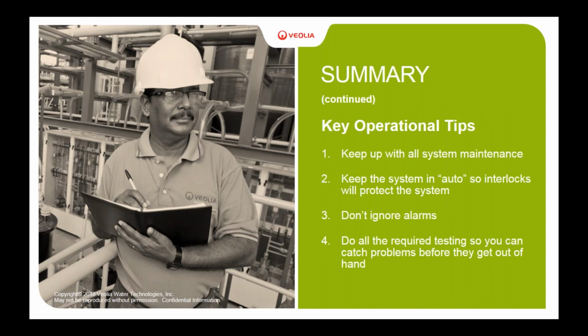Some operational tips that we went over. A lot of this has to do with keeping your system maintained properly. If that's the operator himself or the maintenance department: keeping pH probes calibrated on a daily basis, keeping heat exchangers cleaned, making sure boilers' preventative maintenance work is done, etc. If the system is maintained well and everything is functioning properly, your reactor should perform effectively.